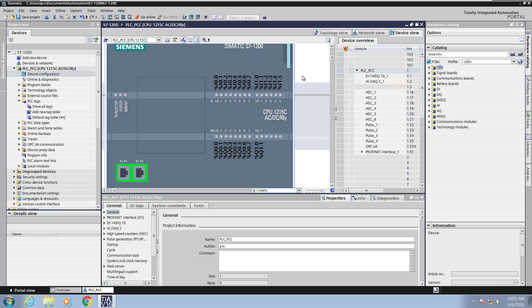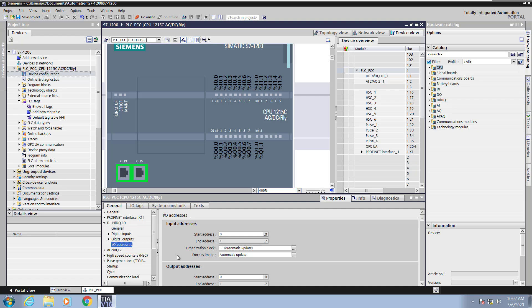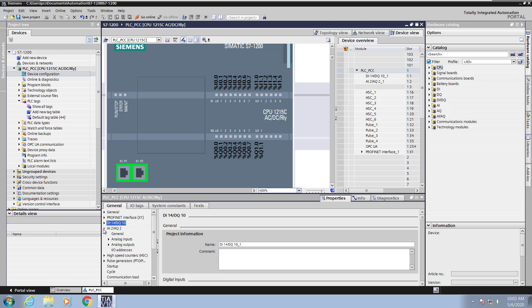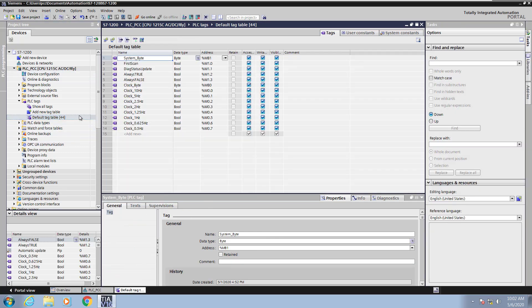At the top of the PLC will be the digital inputs. At the bottom of the PLC will be the digital outputs that are built into the PLC. Down in the CPU properties I'm going to go down to the I/O addresses for the digital input. The starting address is byte 0 for the inputs and byte 0 for the outputs. For the analog inputs that are built in, the starting input addresses are 64, located in the top right-hand corner of the S7-1200 PLC.